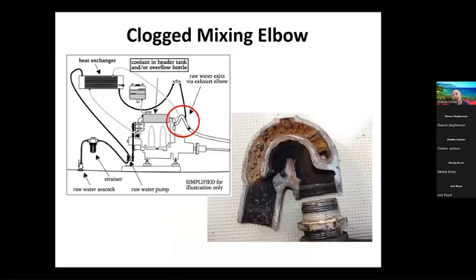Another issue we run into, and people with Yanmars will recognize this, is the mixing elbows. A lot of these mixing elbows aren't made out of high quality metal, usually cast iron or regular steel. Over time, corrosion and carbon build up, and this will cause restricted water flow from the exhaust, or low water flow, where you'll start seeing steam coming out the back. That's all indicators of restricted water flow, and most of the time the mixing elbow is the culprit.